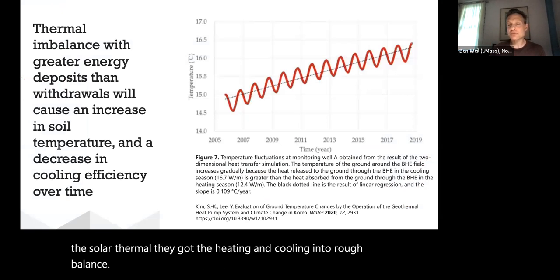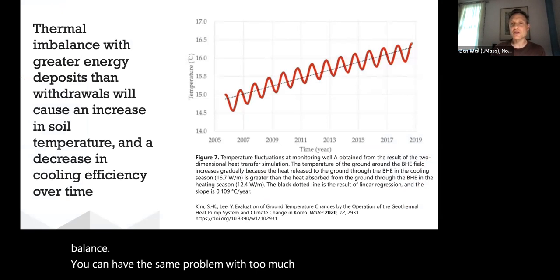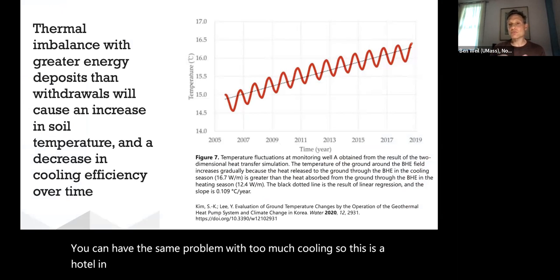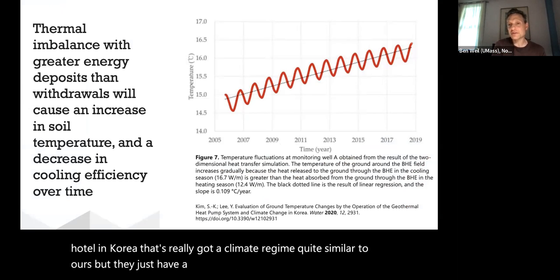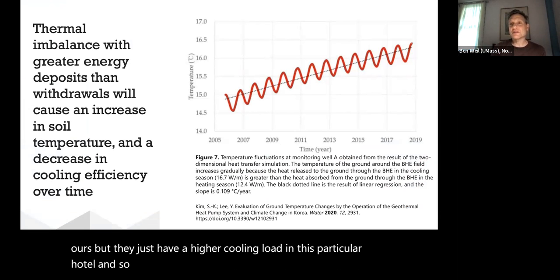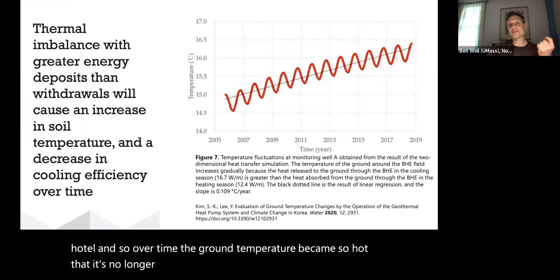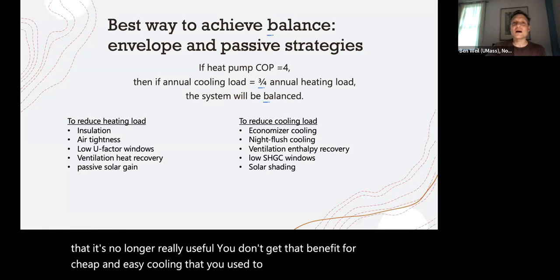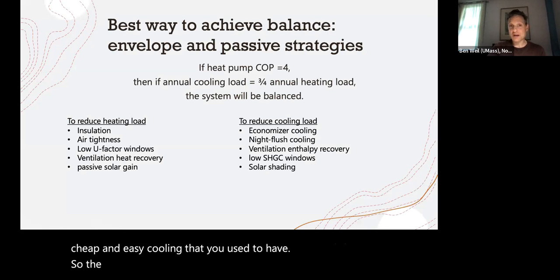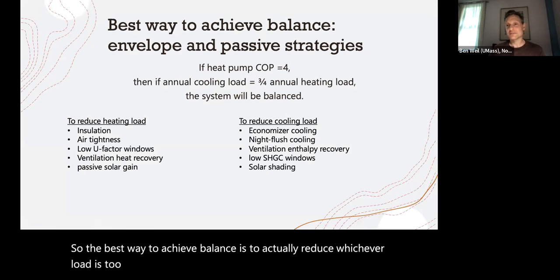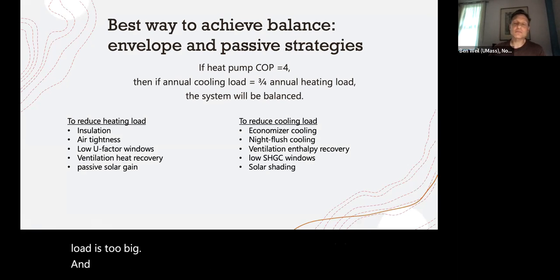You can have the same problem with too much cooling. So this is a hotel in Korea that's got a climate regime quite similar to ours, but they just have a higher cooling load in this particular hotel. And so over time, the ground temperature became so hot that it's no longer really useful. You don't get that benefit of cheap and easy cooling that you used to have. So the best way to achieve balance is to reduce whichever load is too big. And where we are, that tends to be our heating loads.